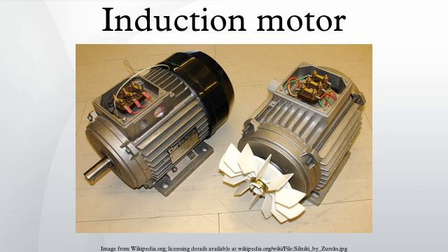Many single-phase motors having two windings can be viewed as two-phase motors, since a capacitor is used to generate a second power phase 90 degrees from the single-phase supply and feeds it to the second motor winding. Single-phase motors require some mechanism to produce a rotating field on startup. Cage induction motor rotor conductor bars are typically skewed to reduce noise.